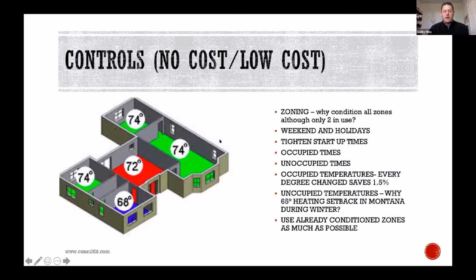This zone might be controlled by a 10-ton unit, and another by a 4-ton unit. If I'm going to schedule a meeting, why not think outside the box as a manager? Schedule the meeting in the zone controlled by the 4-ton unit, not the 10-ton one. There are so many more examples, and I wish I could share them all.